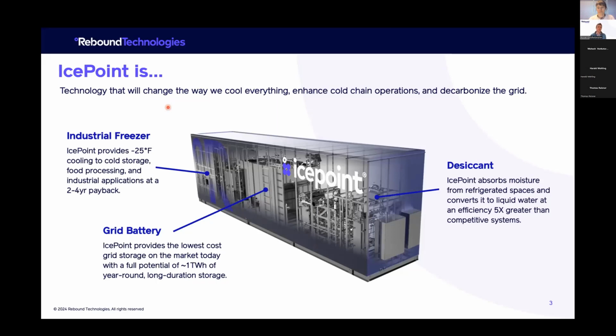In these facilities you have food processors and cold stores doing blast freezing, and they have really transient loads—going way up and way down, by a factor of 3 to 5, pretty regularly throughout the day. Traditional vapor compression systems have a lot of trouble serving that load, so you oversize the system, which represents really wasteful CapEx because that product gets utilized at a pretty low level.